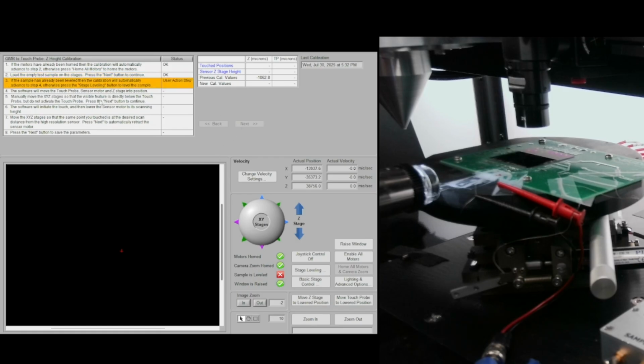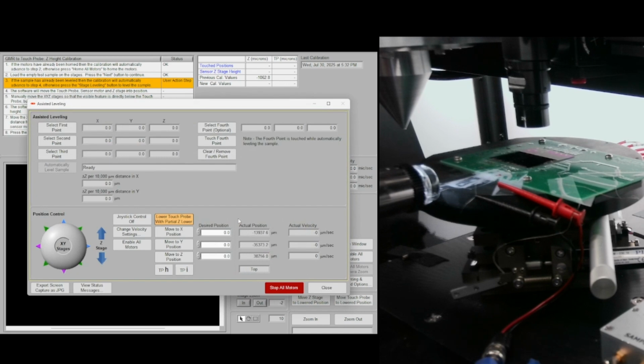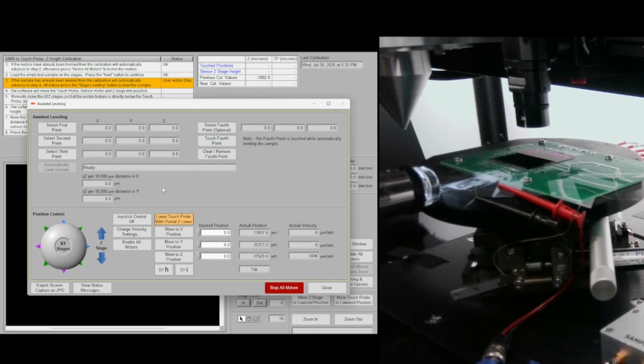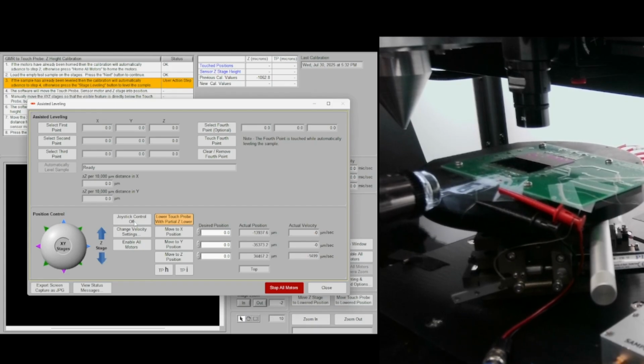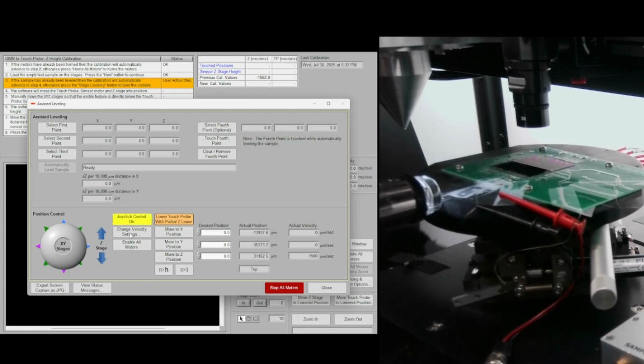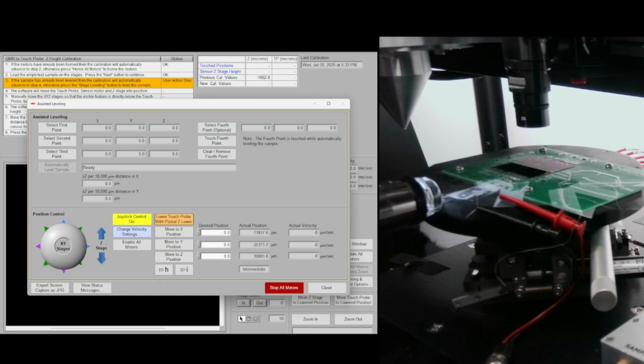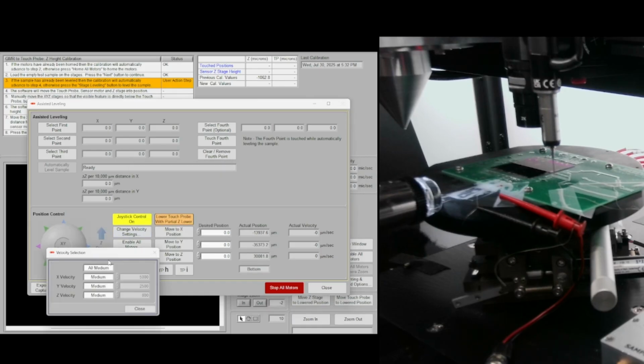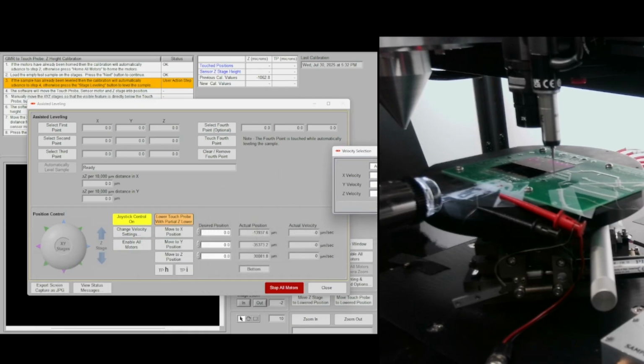At this point, the sample is not leveled, as indicated by the red X. To correct this, we'll go to stage leveling. First, lower the touch probe. I'll turn on the joystick and wait for the probe to lower. I'll keep the speed set to medium and begin selecting the first 3 leveling points. These points should form a triangle within the area you plan to work on.